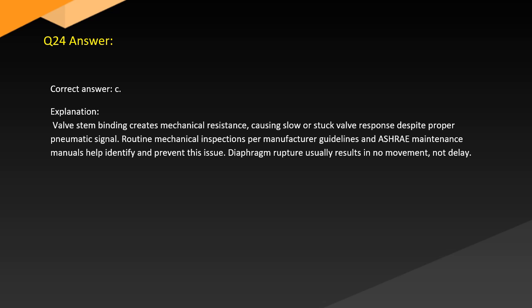Answer. Correct answer: C. Explanation. Valve stem binding creates mechanical resistance, causing slow or stuck valve response despite proper pneumatic signal. Routine mechanical inspections per manufacturer guidelines and ASHRAE maintenance manuals help identify and prevent this issue. Diaphragm rupture usually results in no movement, not delay.